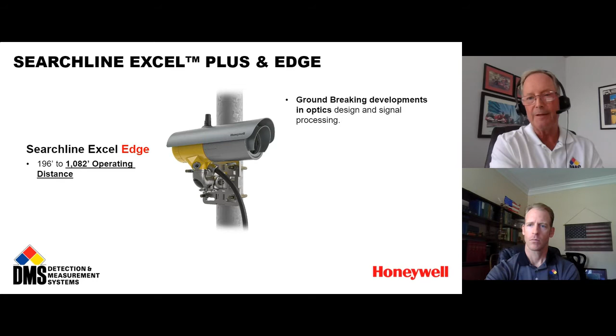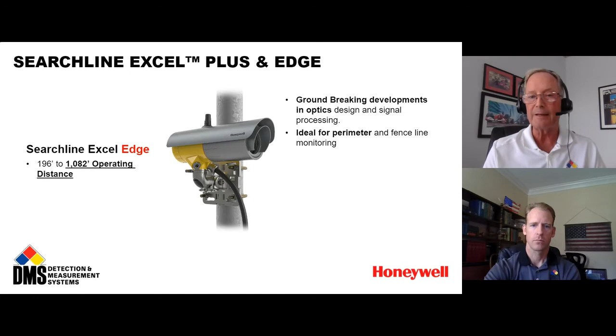This makes this, particularly the Edge, ideal for perimeter monitoring. For example, if you've got a fence line where you're concerned about gas traveling over to a neighbor's property, being able to shoot at that extended distance really does help tremendously and bring the cost down for that kind of perimeter monitoring. Or if you're just monitoring the perimeter of a process area, and sort of enclosing a process area, or shooting down the walkway through the middle of a process area. Those are the sort of applications that we're talking about. But to put this in the proper perspective, you can use a single Searchline Excel Edge where you would have to use at least two and even three competitive open path detectors to accomplish the same distance that you're trying to monitor.